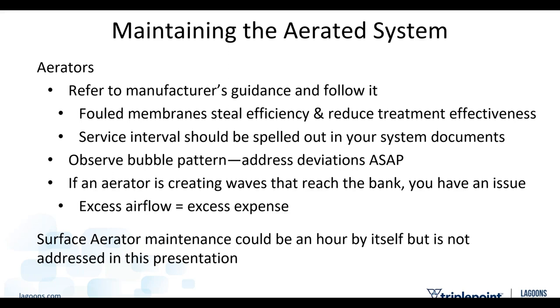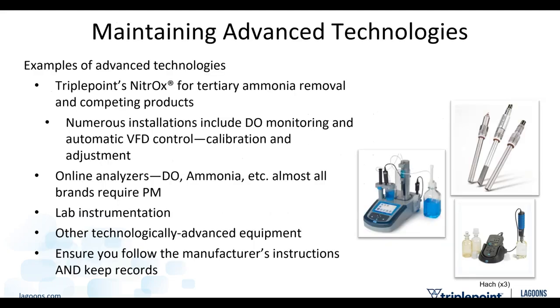As far as aerators are concerned, keep an eye on your bubble pattern. When they're brand new, it is fantastic if you can take a picture on your cell phone so that when you're out there again, you can compare right there, stand in the same spot. Does it look like my picture? Yes or no? Yes, all good. No, let's figure out what's wrong. And I'll tell you right now that if surf's up on your pond, if you've got waves crashing on the shore, if you're seeing little white caps that aren't coming from the wind, you have an issue. You have a problem with an aerator. And again, excess airflow is just extra expense. I think we could probably spend an entire hour on surface aerators and maintaining them. We're just not going to get there in this presentation though.